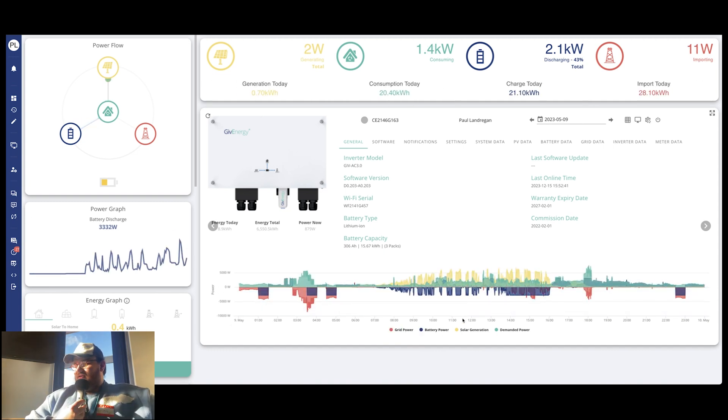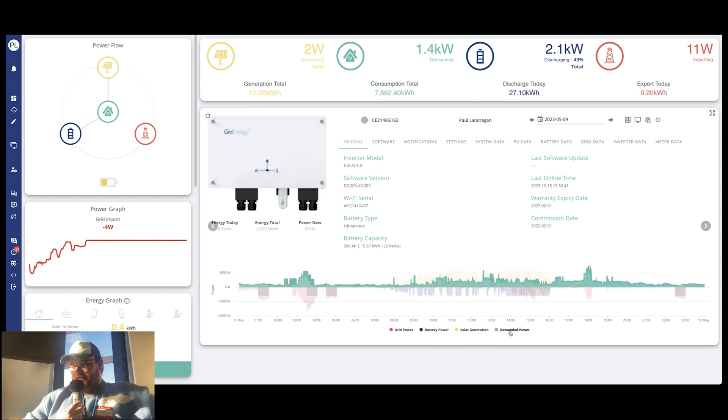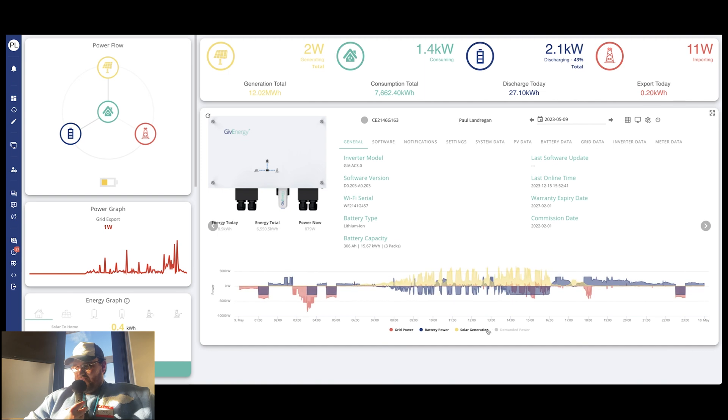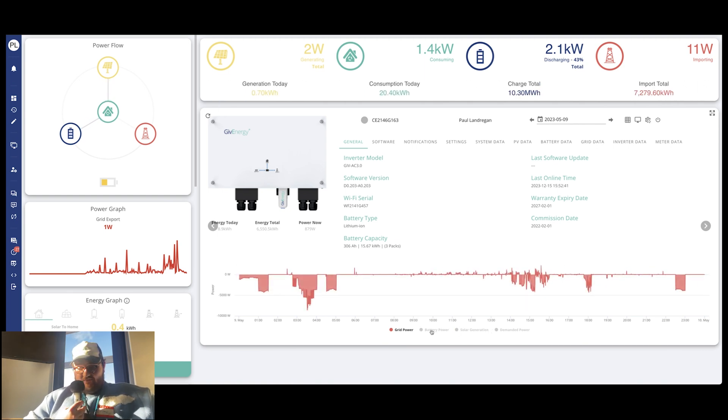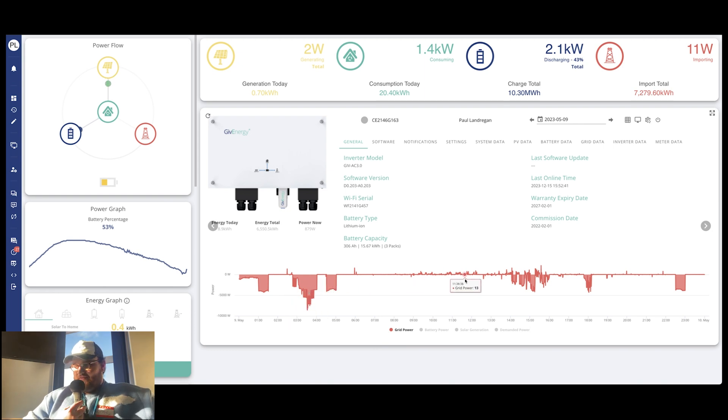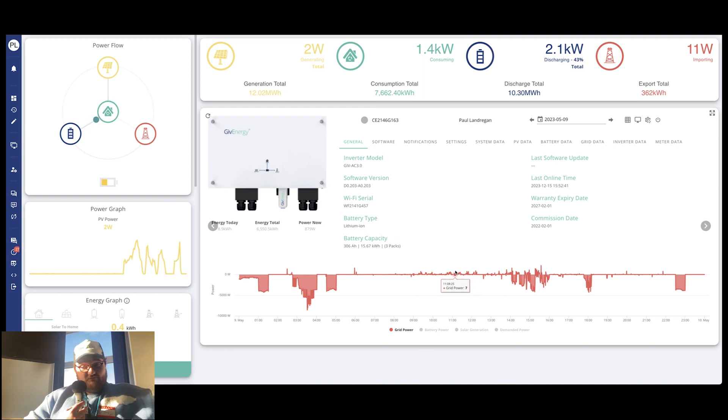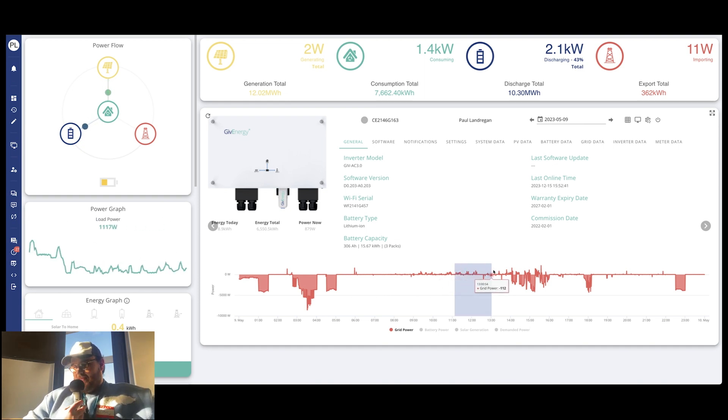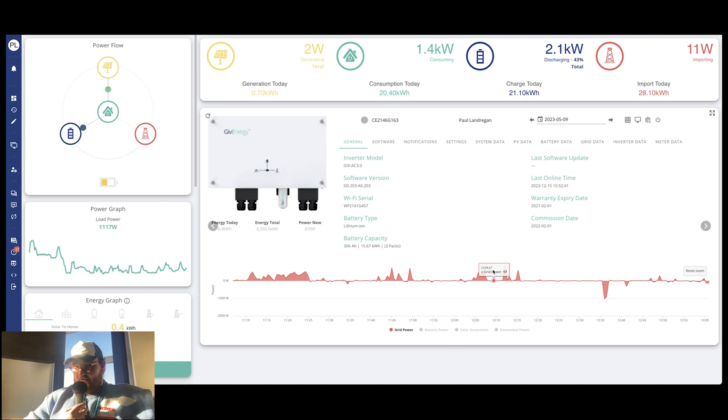One thing I think that is not the clearest, so I'll try and clarify for you now. If we just get rid of all of these and just have grid power, you can see sometimes it's pulling down from the graph and sometimes it's shooting above. That is the signifier that you're either importing or exporting. So if it's pointing downwards, that means that we are taking it from the grid and it will show as a minus. If it's pointing up, that means we are sending it back and it will show as a positive.